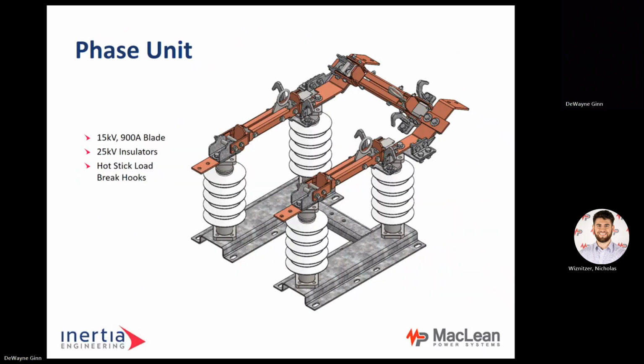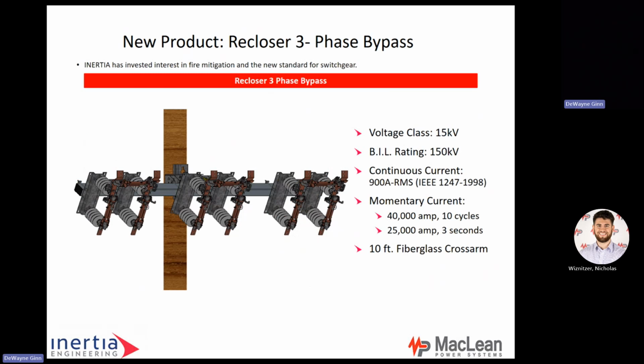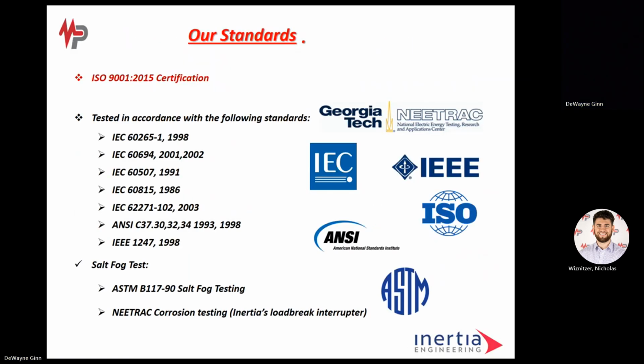Single phase units, or a phase unit for a disconnect. We built these recently and they're in our portfolio for 15 and 25 kV, 600 to 900 amps. You can utilize these over a set of reclosers. This would be a three-phase set with the reclosers, and take reclosers offline with them. Again, momentary is 40,000 amps, 10 cycles, 25,000 amps, 3 seconds, all the way around. Again, it's something that's available to you at this point.